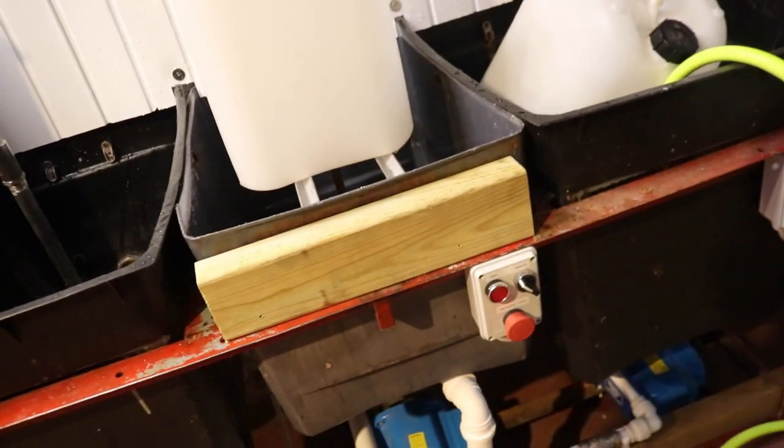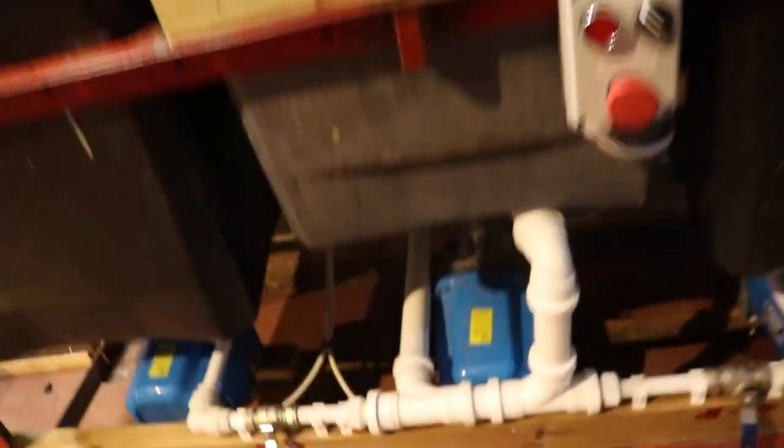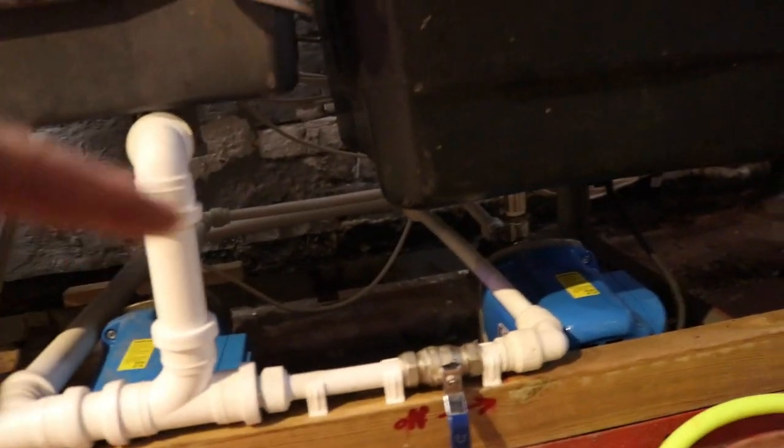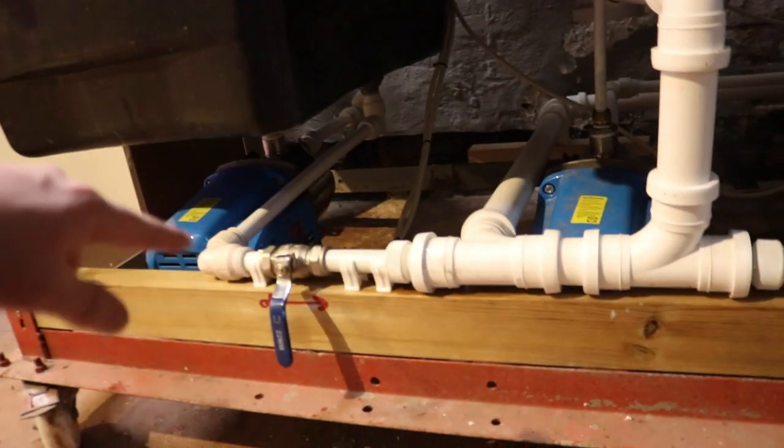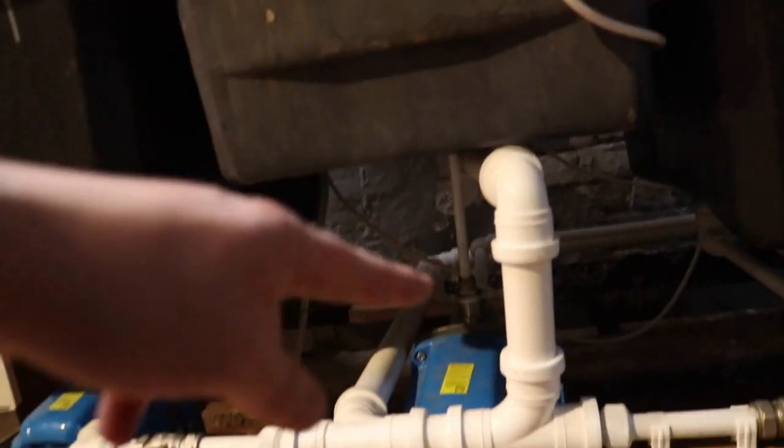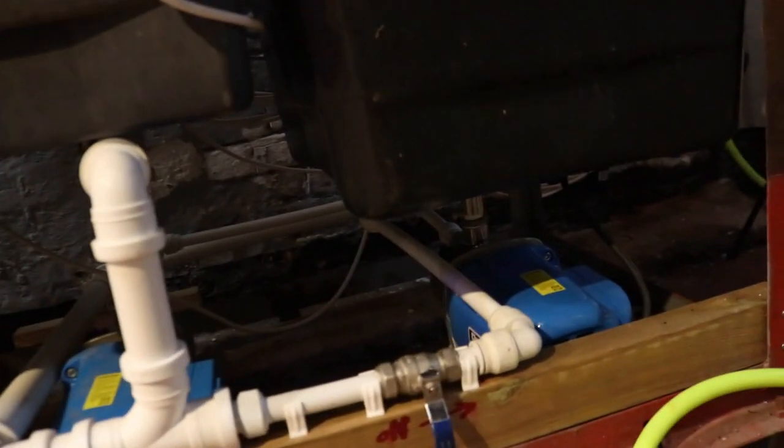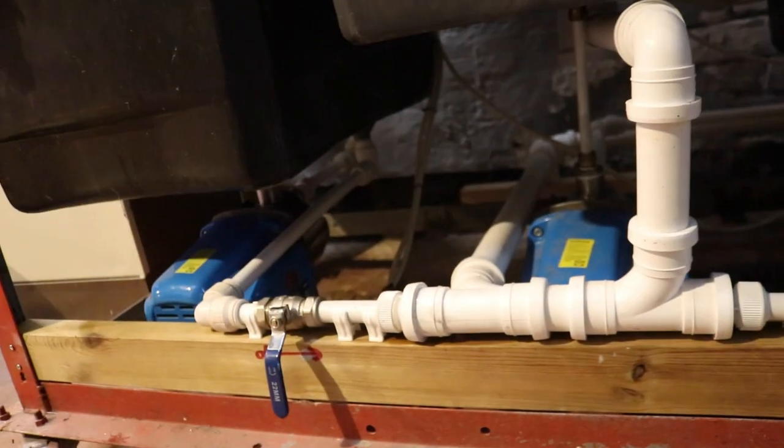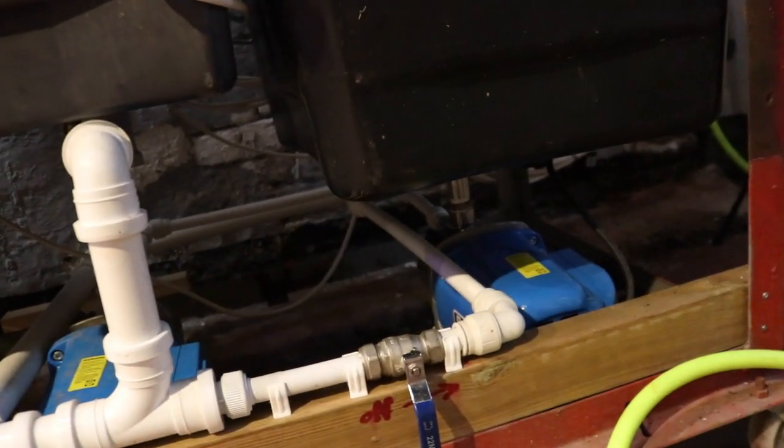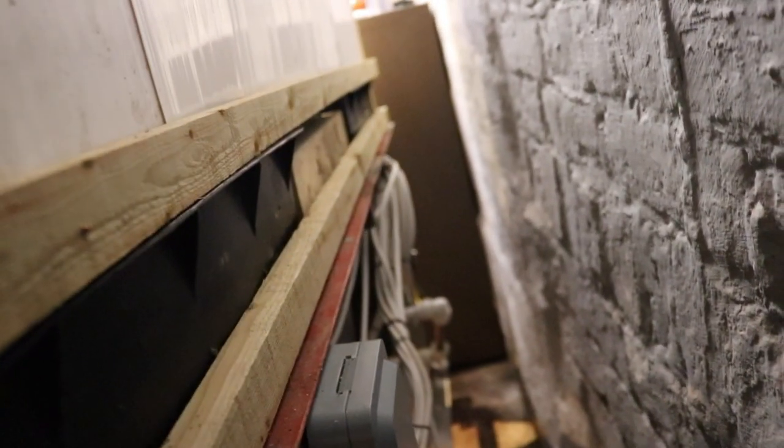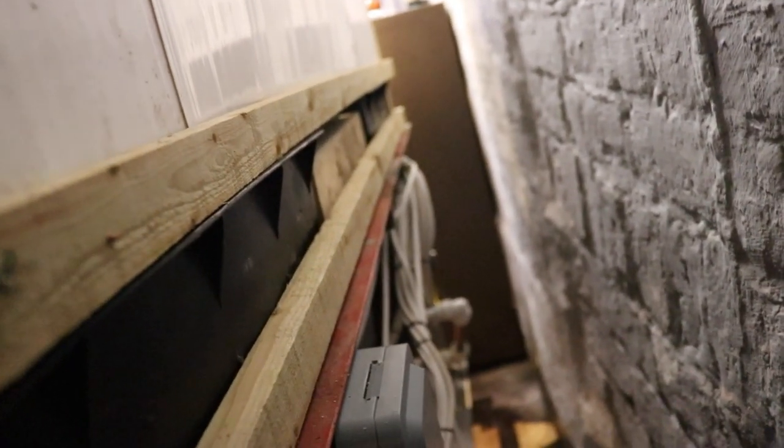Obviously with the caustic tank and the acid tank, they're pulling on their own reservoir so they just pump immediately when they're turned on, but the exact same concept. Then down below we've got drain valves to drain both tanks, main drain valve to drain the rinse tank, and then the three pumps just sat there nice and accessible. So if we need to repair, change or alter any of it that's doable. Then just a quick peek around the back, you can see we've got a plug here for the acid pump. This is the pump that needs the most maintenance because over time there's a brass bushing in there that gets eaten by the acid.